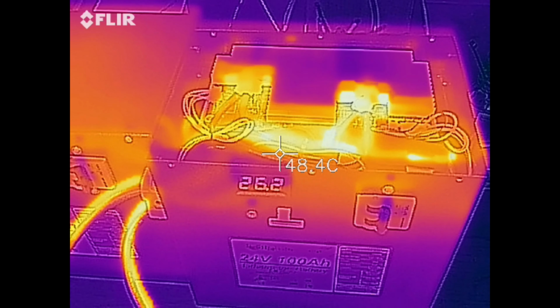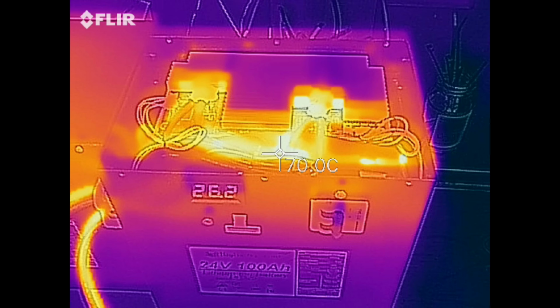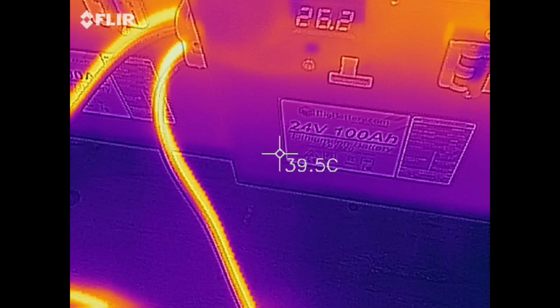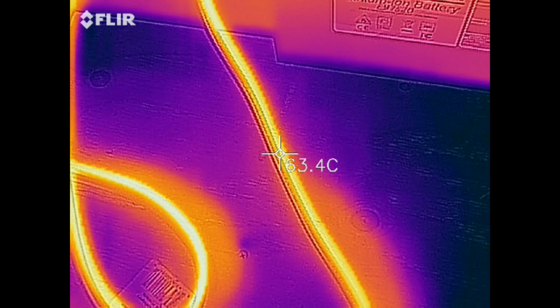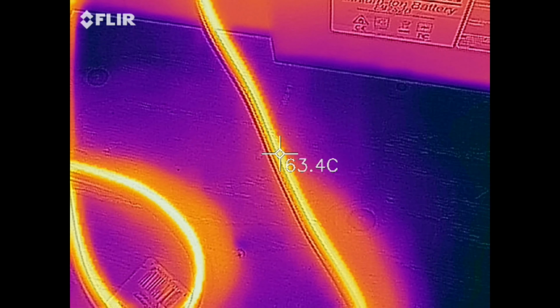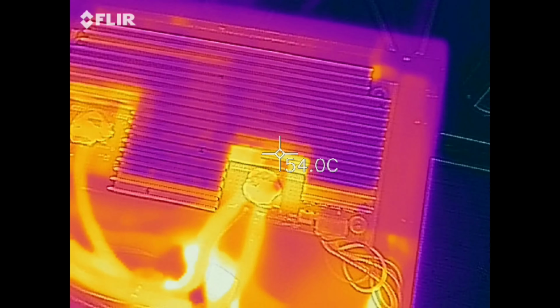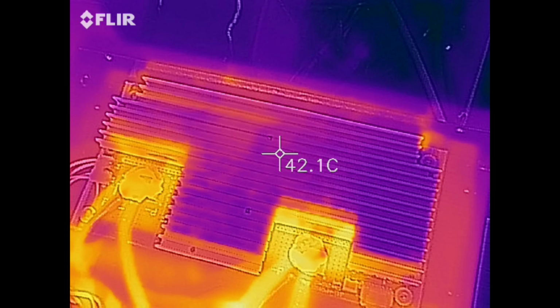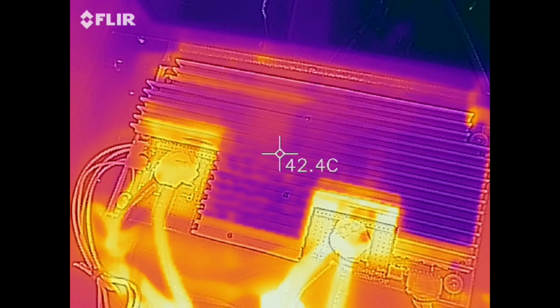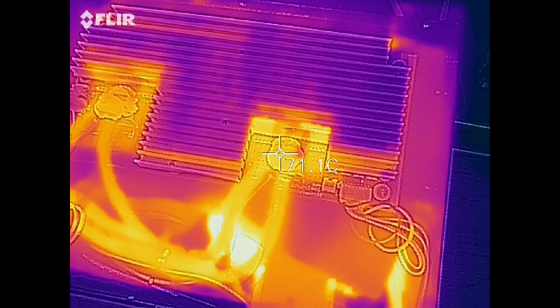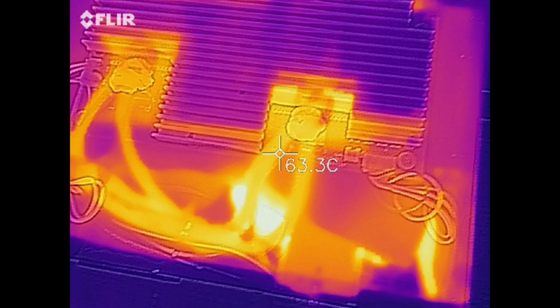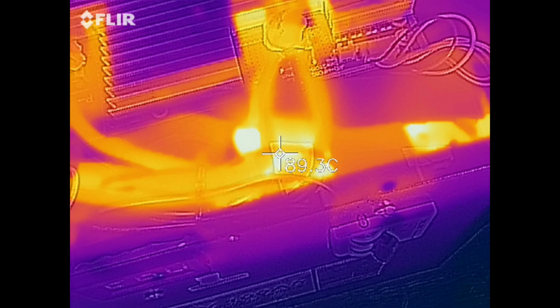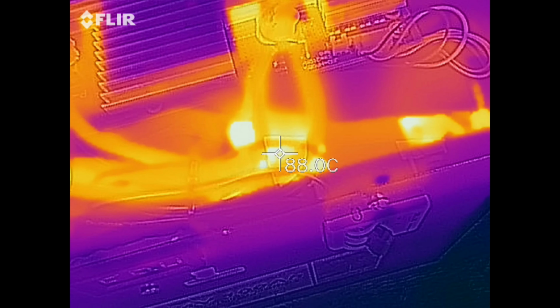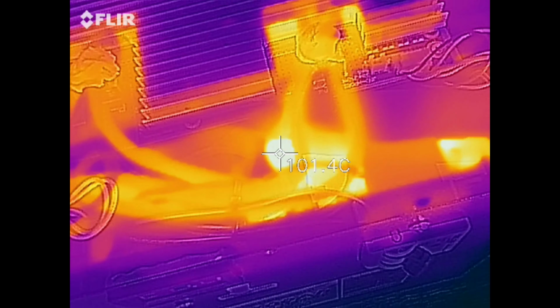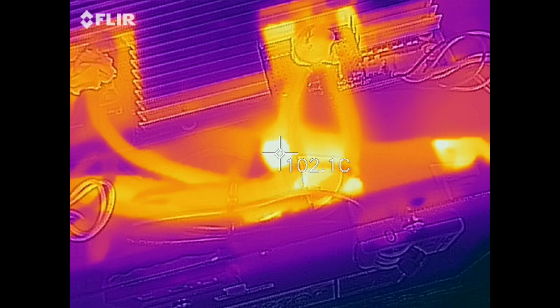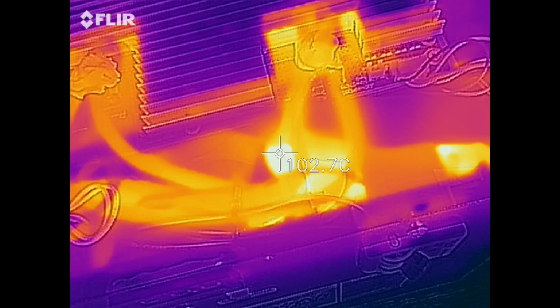Alright guys, so we're about 10 minutes into this test now, and you can see it is getting extremely warm. So I noticed the 6-gauge cable down here. You know, we're sitting at approximately 63 to 64 degrees Celsius on this cable. Now if you have a look inside here, the heat sink on the BMS itself is nice and cool, sitting around 41 to 42 degrees Celsius. The terminal is a little warmer, around 70. But down here, alright, this is the connection on the side of the circuit breaker. We're at 88, 90 Celsius. Oh, there's 101 Celsius, 102. So there's definitely a problem going on down there.